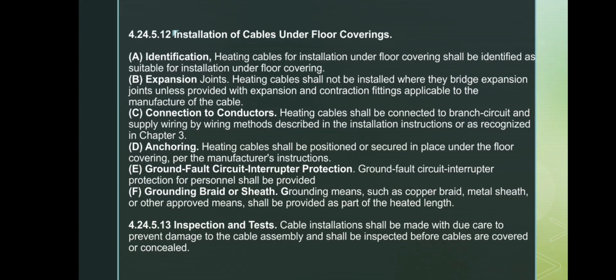A grounding method, such as a copper braid or metal sheath, must be included along the heated length. Finally, all cable installation must be carefully inspected before being covered or concealed to ensure that no damage has occurred.